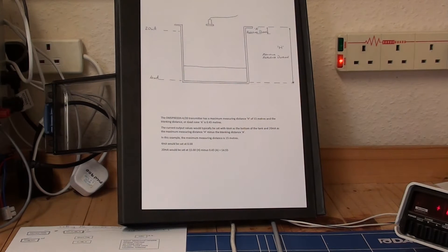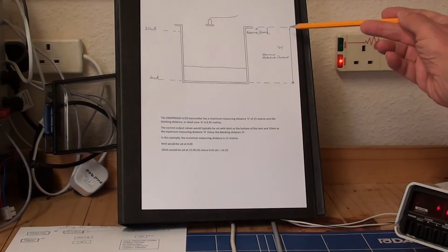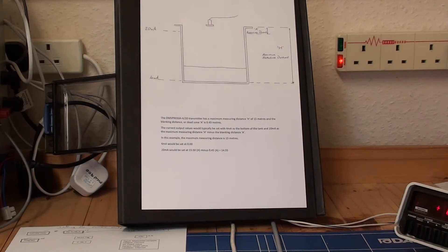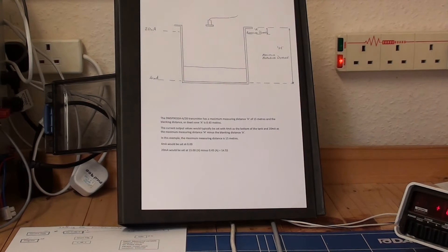So in this instance we're going to set up the current output for 4 milliamps to be the bottom of the tank, and 20 milliamps will be distance H — 15 minus the blanking distance of 0.45 meters. So 4 milliamps we're going to set up at 0 and 20 milliamps is going to be set up at 14.55 meters.